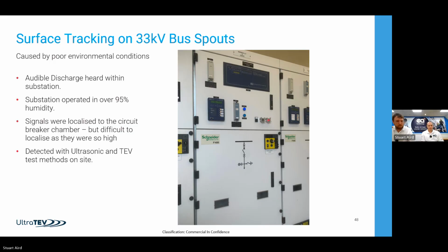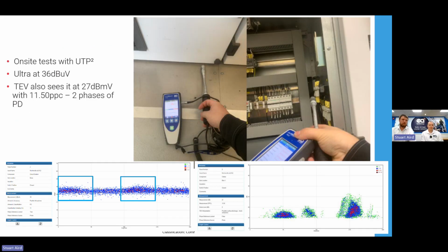In terms of what is detected, with UTP2, the ultrasonic was at 36 dB. We care when things go above 0, really. We really care by the time it's 6. So at 36, just to give you a few orders of magnitude away, that's significant.